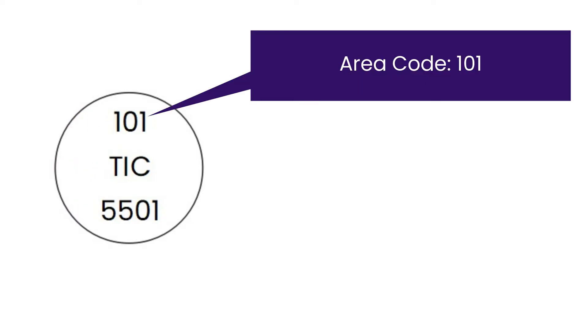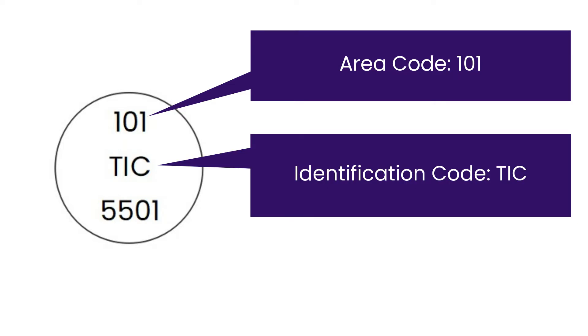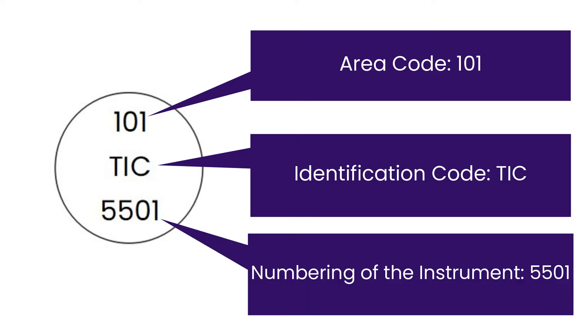We can also see some symbols like this. These symbols are made with three different parts. First is area code, that is 101. Second is parameter identification code, that is TIC, temperature indicator controller. And third is loop number in control system, in this case, numbering is 5501.